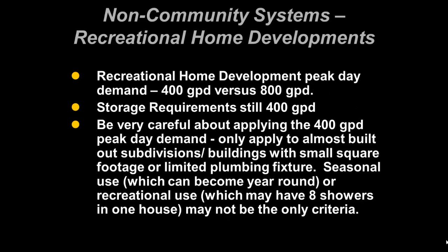Many of you will perform sanitary surveys for recreational home developments. Many of these systems may request a reduction in their source and storage demands, but we issue caution in doing this. Please consult with the Division of Drinking Water if asked to lower these requirements. Table 510-1 allows for a reduction for the source demand for recreational home developments, but without extensive data to support this claim, we recommend that this reduction not be made. We find that many of the recreational home developments start out as second homes, but soon turn into full-time residential developments requiring substantially more water.